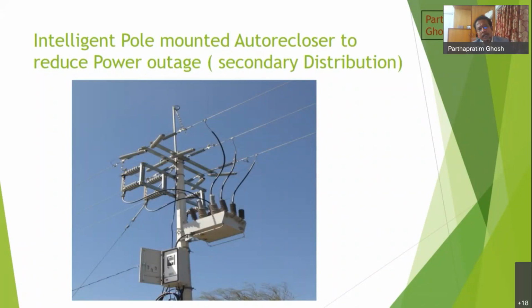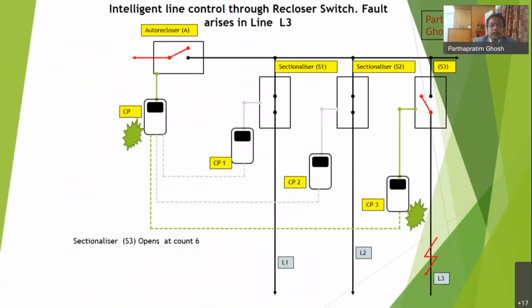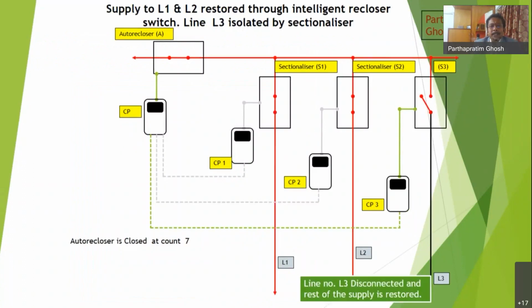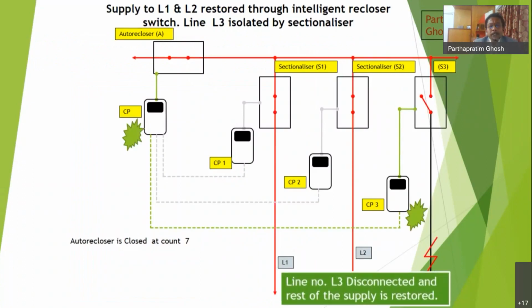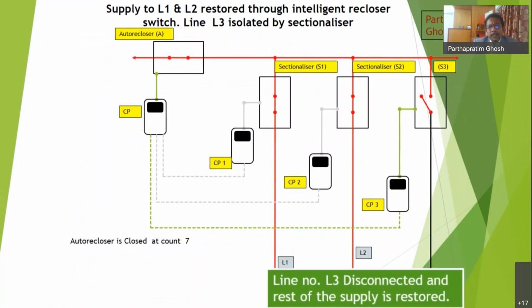This is a very specialized and intelligent special application switchgear and circuit breaker. This is a pole mounted auto recloser. This in itself is a very intelligent circuit breaker and a smart switchgear. Schematically, in a simple way, let us understand how an intelligent auto recloser works. Auto recloser is a smart switchgear which can automatically switch on and switch off.